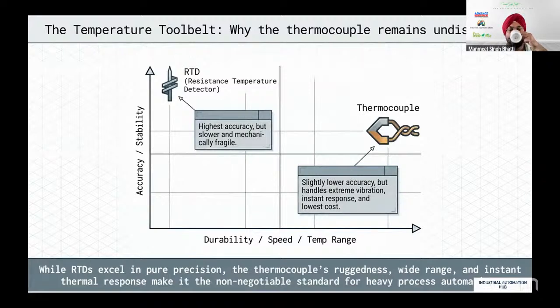Now, there is also a comparison that people make, whether I should be using an RTD or a thermocouple. I would say you are the best judge of yourself, of what you want, how you want, and where you want to install it. I have found RTDs more accurate, but RTDs also fail a lot. They work well, they have good response, they have good accuracy, but they fail a lot.